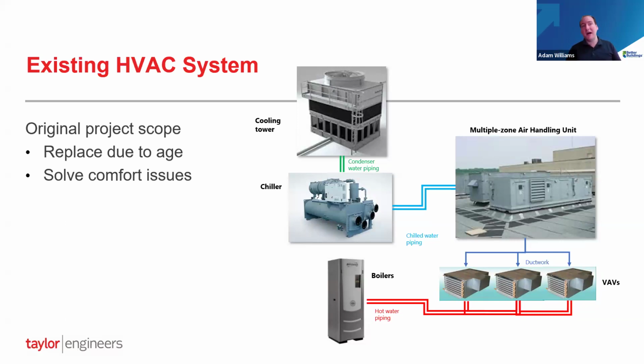And that's served by a natural gas boiler. That's the existing system. The original project scope on this was to basically do a full gut retrofit, provide modern equipment with modern controls, primarily to resolve a lot of comfort issues they were having due to the old equipment. And then also solve some zoning issues, rezone some of the terminal units around to solve some additional comfort problems. So that was the original scope.